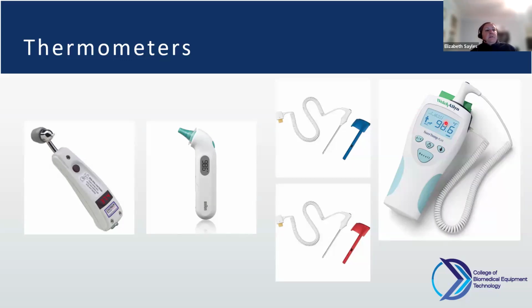In terms of maintenance for these, it's really just a function check. Welch Allyn has a calibration key that they provide to their customers. When you pop the probe well out of the back of the thermometer and unplug the key of the probe, you'll plug in the calibration key. If you look at the set of directions attached to the probe key, it'll tell you what temperature the thermometer should read once you plug it in. If it's outside of the tolerance listed there, that's when you would work with Welch Allyn to figure out what's wrong with it.